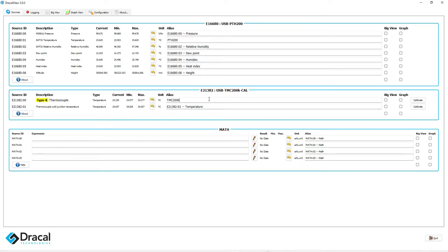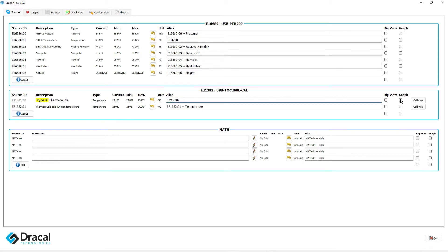It is suggested that you validate the measures before logging them using a graphical interface. To do so, check the Graph box in front of the appropriate channels, and click on the Graph View tab.